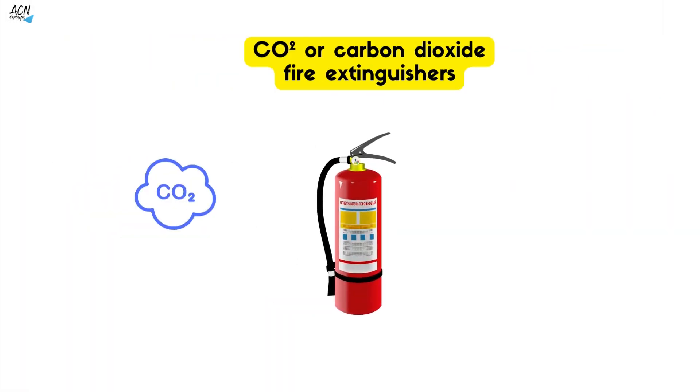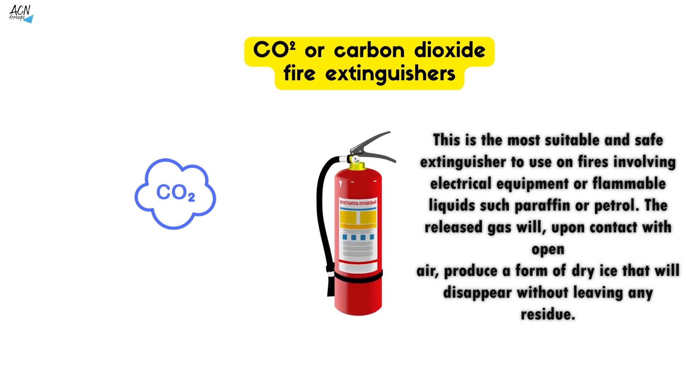CO2 or carbon dioxide fire extinguishers: this is the most suitable and safe extinguisher to use on fires involving electrical equipment or flammable liquids such as paraffin or petrol. The released gas will, upon contact with open air, produce a form of dry ice that will disappear without leaving any residue.